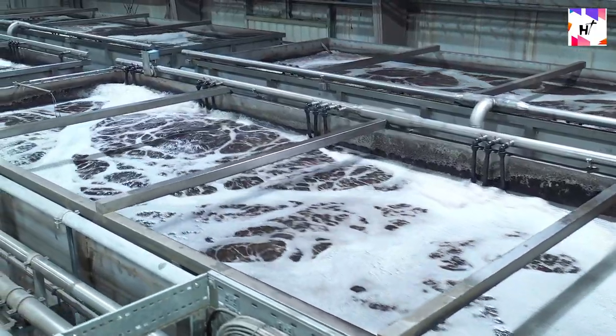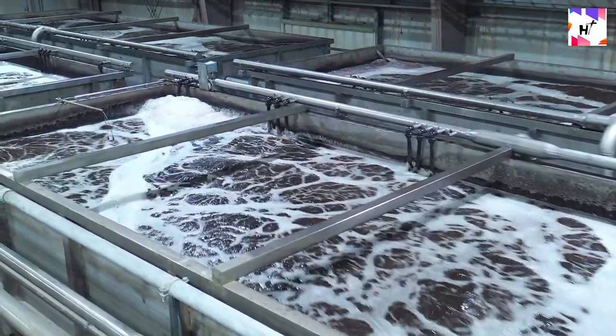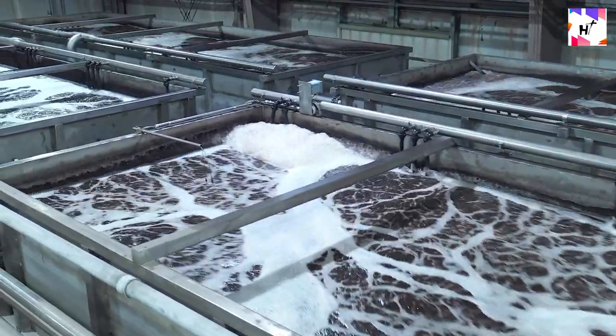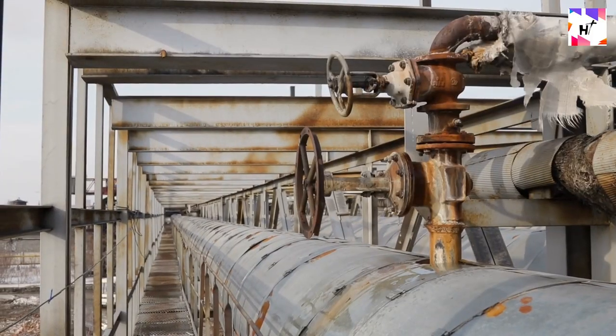The subsequent event takes place at the air blower. Two air blowers are normally installed in the biofilter reactor, with one acting as a backup. These blowers are in charge of delivering air in the form of air bubbles, which helps microorganisms form. Furthermore, it helps with back draining the sludge, moving the sludge from the sedimentation tank and giving air to the activated carbon tank. Before being released into the ocean, the treated sewage must first go via the discharge pump.